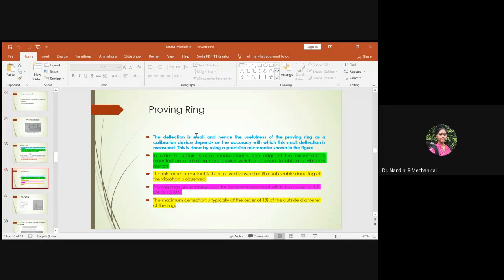The deflection obtained is always small, and hence the usefulness of the proving ring as a calibration device mainly depends upon the accuracy with which this small deflection is measured. This ring is basically useful to get a very accurate value for a very small amount of deflection, meaning it can sense accurately even a very small deflection.